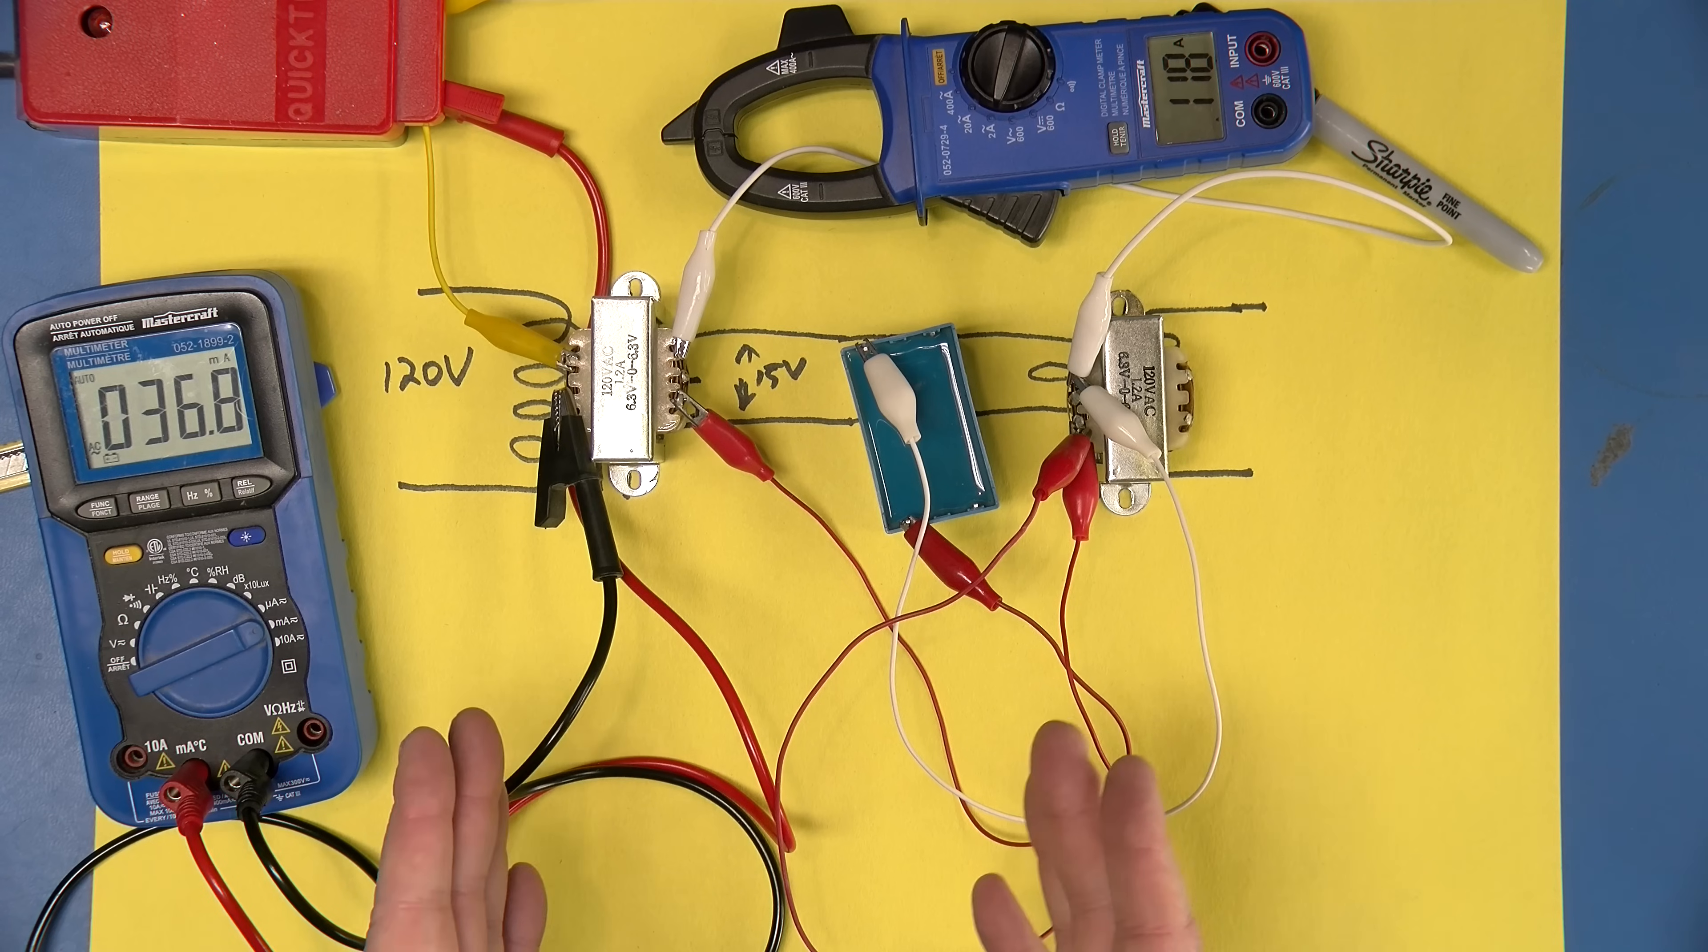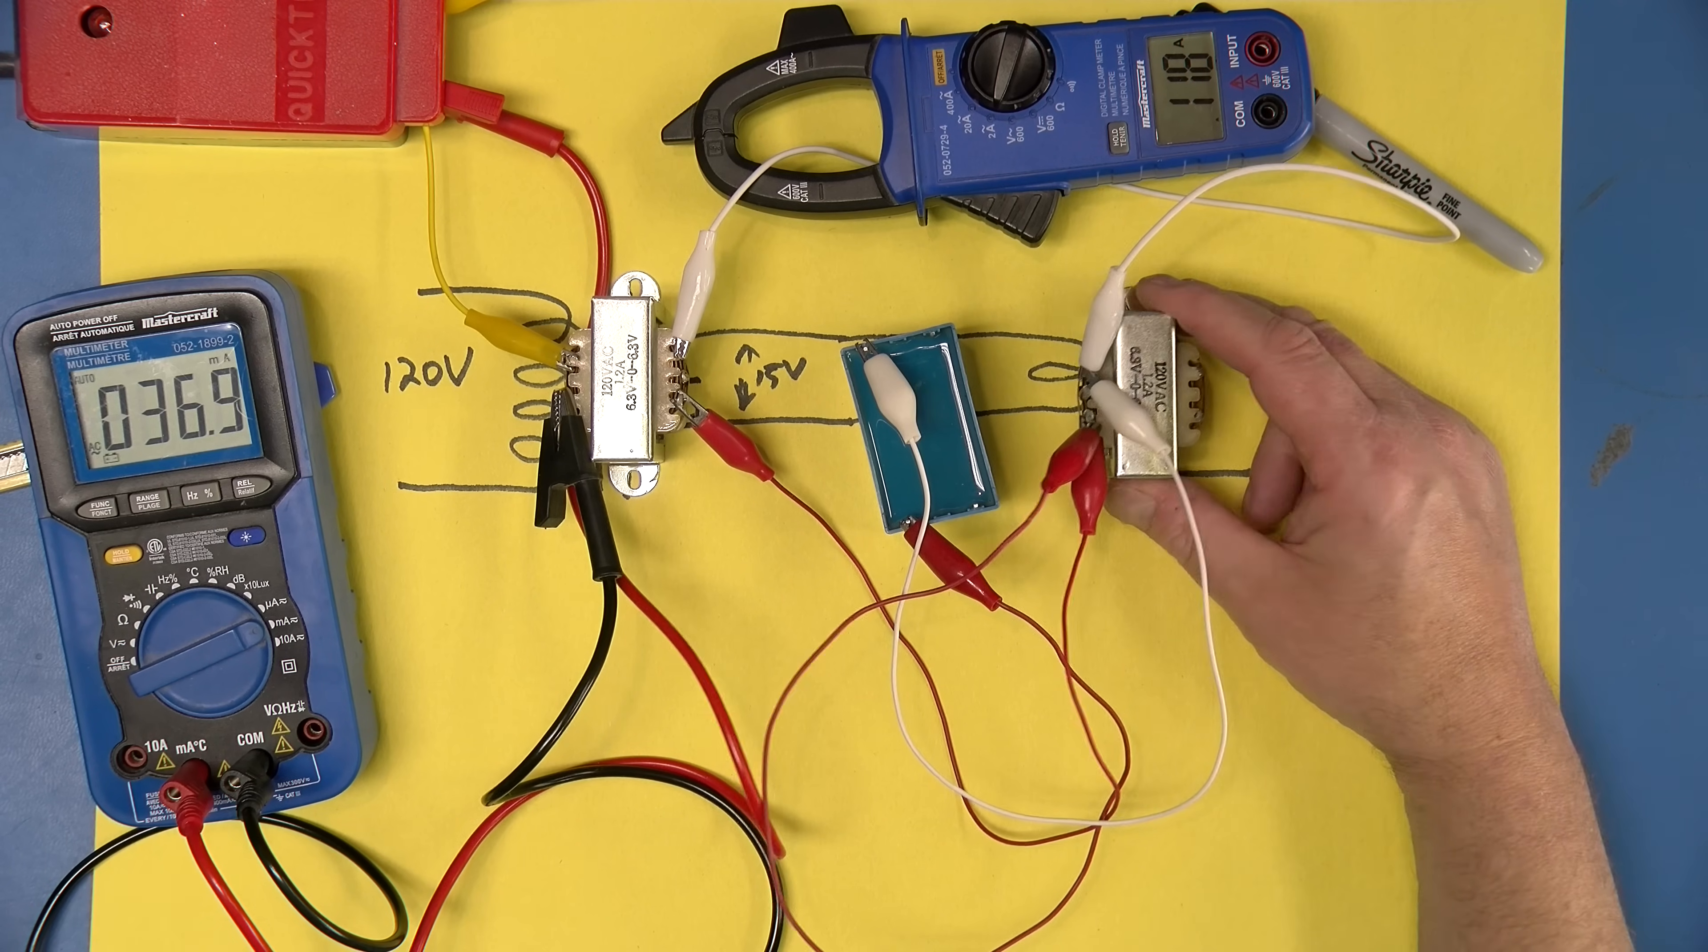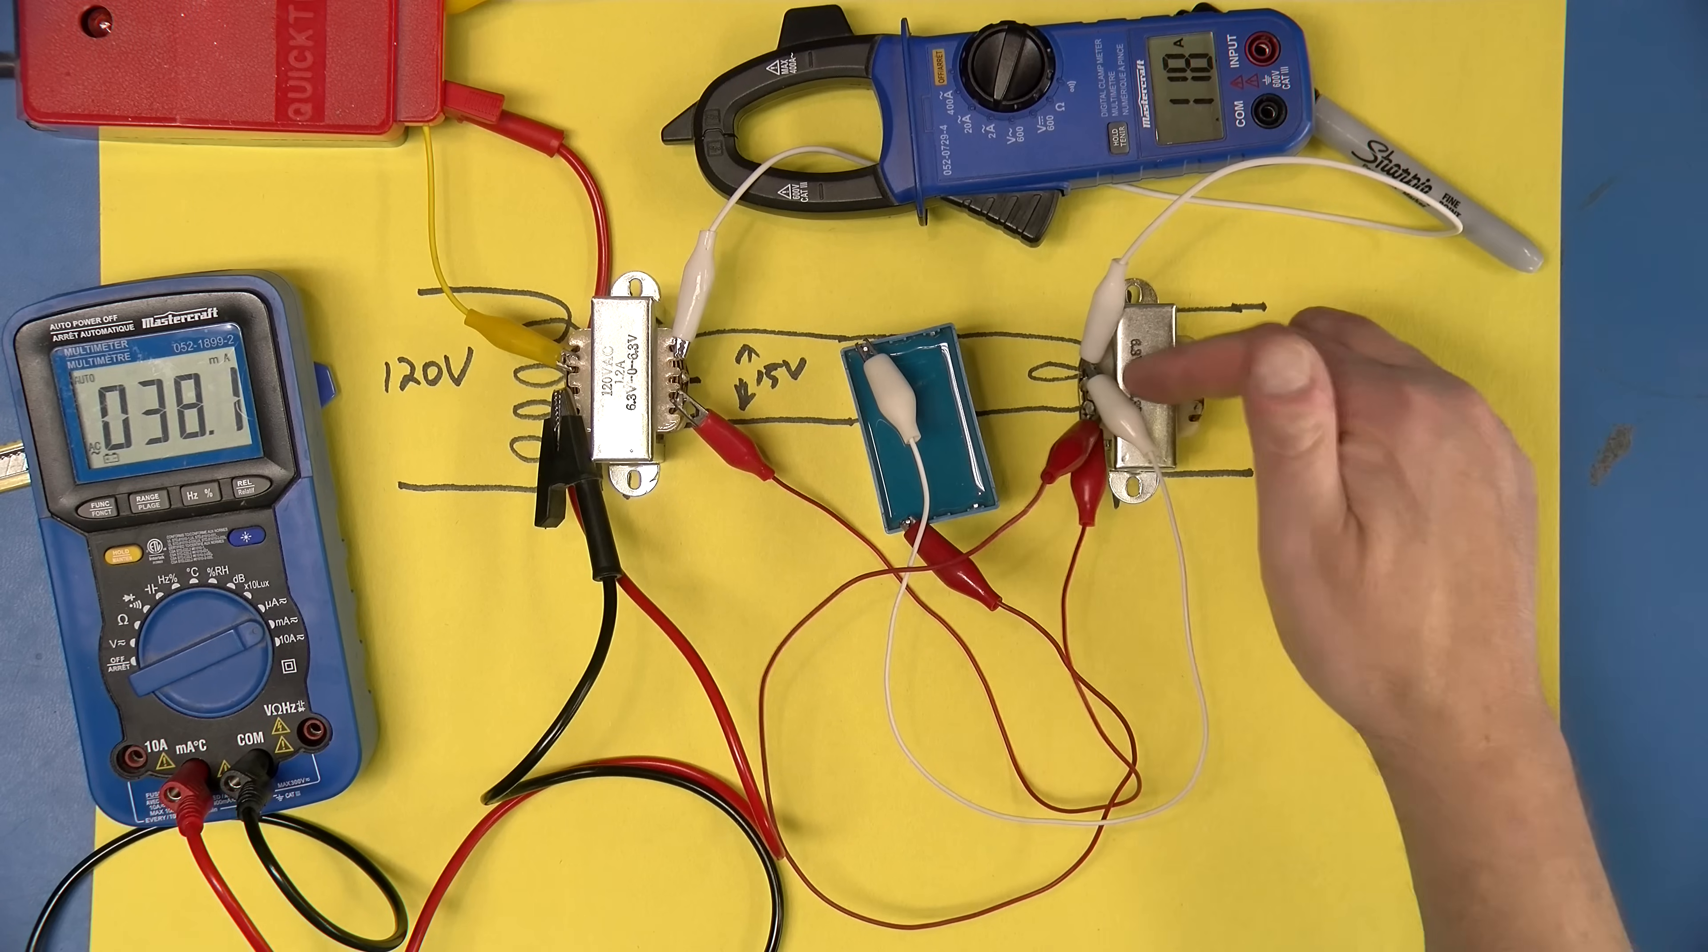So that will somewhat alleviate the problem, but not completely. We can't make this second current completely go away, because no matter what we do in terms of trying to cancel out the inductive current of this transformer, there will always need to be some real current to supply the power losses in there. And indeed, it turns out that the capacitor I've selected is about right to largely get rid of the inductive current, but still leaves the real current carrying the lost power to this transformer.